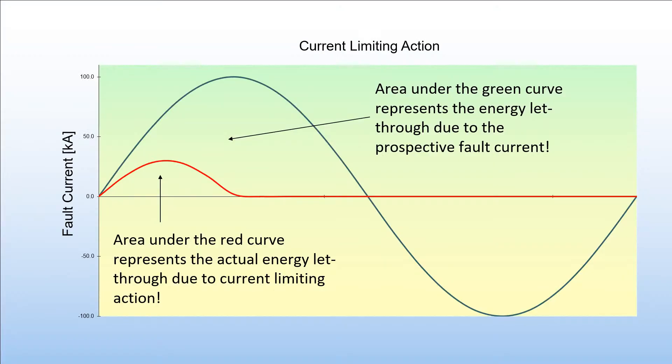Here we can see what current limiting is all about. The green curve is the prospective fault current—in other words, the fault current that would have flowed had there been no current limiting action. The red curve is the actual fault current, and you can see that the peak of the actual fault current is way less than that of the prospective peak due to the current limiting action. Also, the area under the red curve, which is the let-through energy, is way less than the area under the green curve—this is the energy that would have been let through had there been no current limiting.